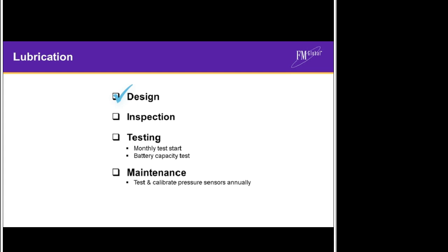From an inspection perspective, lube oil systems should be subject to daily plant inspections and all valves should be secured to prevent accidental closure. Batteries should be inspected at least weekly and should be tested on a varying basis depending on the battery technology. Flooded lead acids and NICADs should be capacity tested on a 5-yearly basis, and valve regulated lead acid batteries should be capacity tested every 2 years or replaced every 3 to 4 years. The emergency lube oil test system itself should be tested for a start-stop functionality on a monthly basis. From a maintenance perspective, it is advisable at major turbine outages to confirm the flow and pressure of the emergency lube oil system.